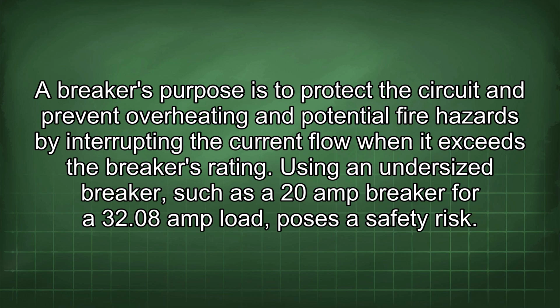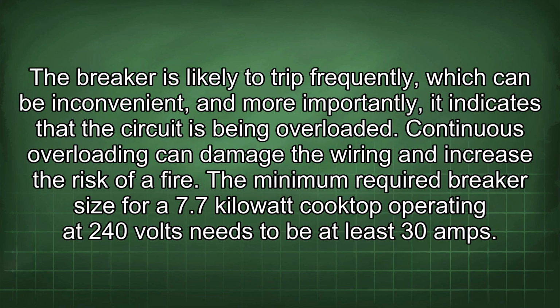Using an undersized breaker, such as a 20 amp breaker for a 32.08 amp load, poses a safety risk. The breaker is likely to trip frequently, which can be inconvenient, and more importantly, it indicates that the circuit is being overloaded. Continuous overloading can damage the wiring and increase the risk of a fire.